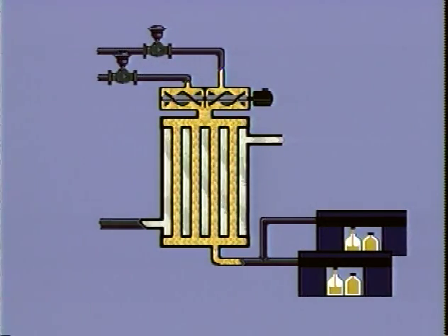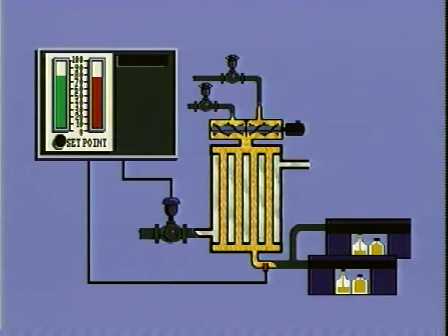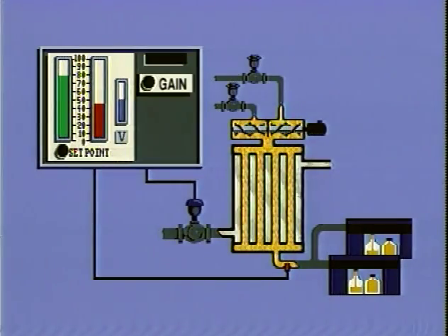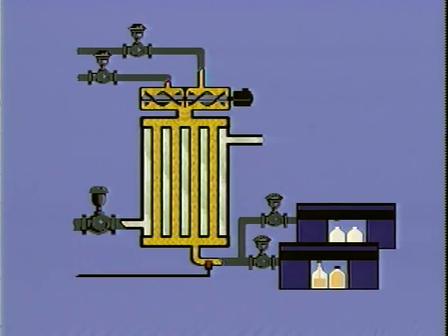After leaving the heat exchanger, the blended product then flowed through a pipeline to 2 automatic bottling machines. Temperature control was first attempted with an on-off controller, but on-off control quickly proved to be totally inadequate for the continuous process. The company then installed a proportional-only controller. The gain of the controller was adjusted so the control valve admitted the right amount of steam to the heat exchanger to maintain the desired temperature. This controller worked well until one of the bottling machines was started or stopped. These load changes to the system created temperature offsets, resulting in a loss of product due to temperatures that were either too low or too high.